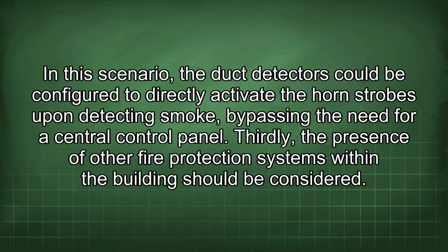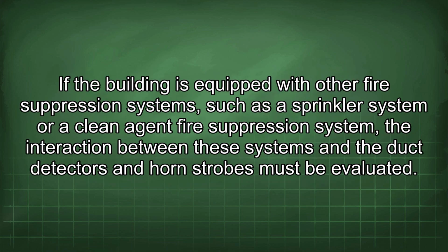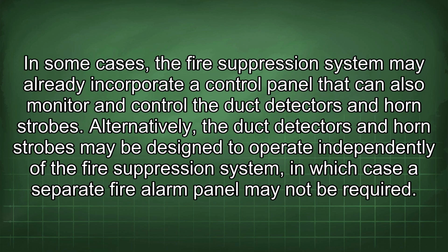Thirdly, the presence of other fire protection systems within the building should be considered. If the building is equipped with other fire suppression systems, such as a sprinkler system or a clean agent fire suppression system, the interaction between these systems and the duct detectors and horn strobes must be evaluated. In some cases, the fire suppression system may already incorporate a control panel that can also monitor and control the duct detectors and horn strobes. Alternatively, the duct detectors and horn strobes may be designed to operate independently of the fire suppression system, in which case a separate fire alarm panel may not be required.